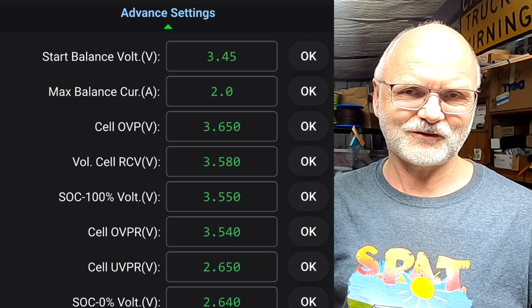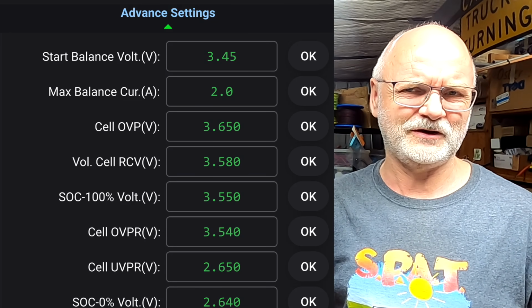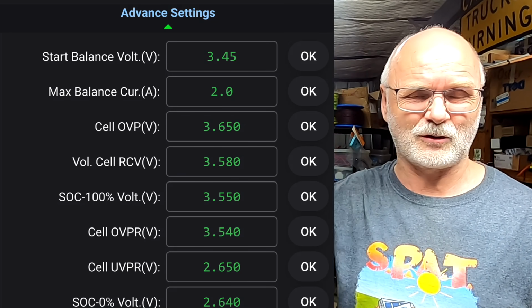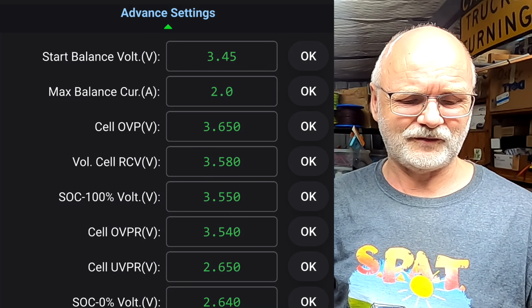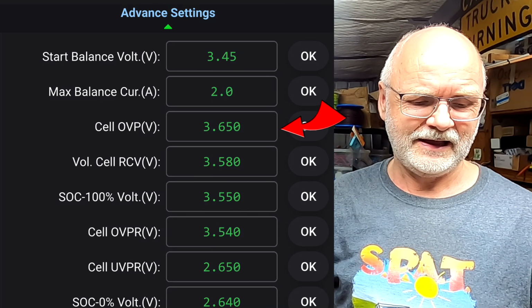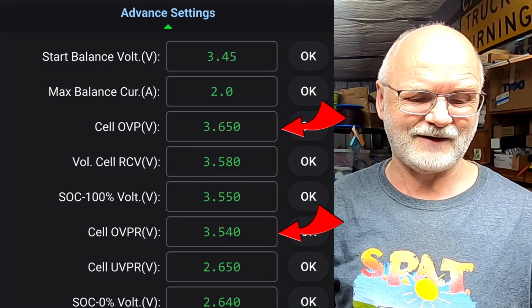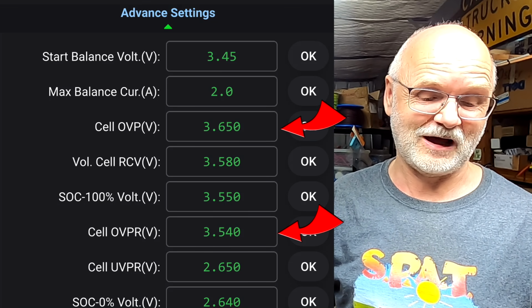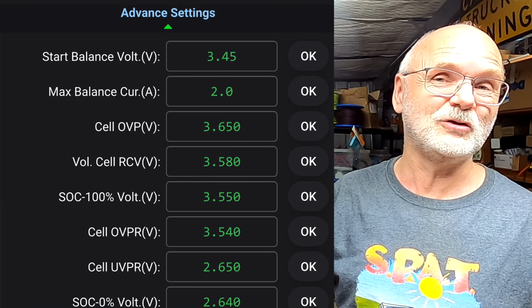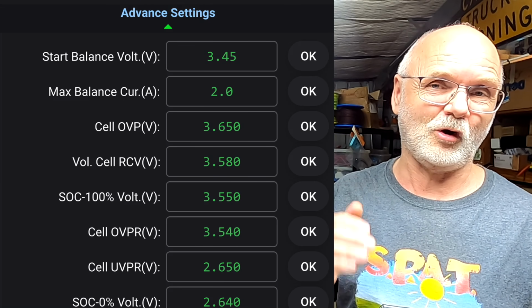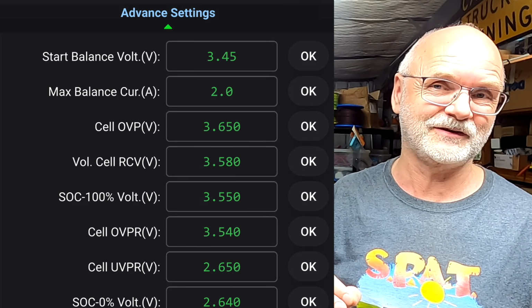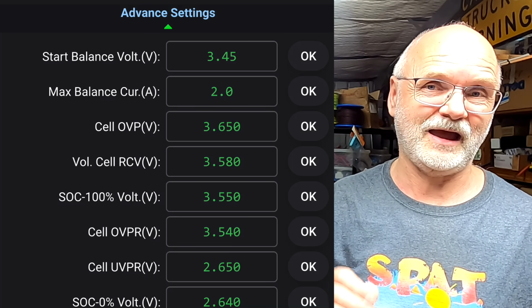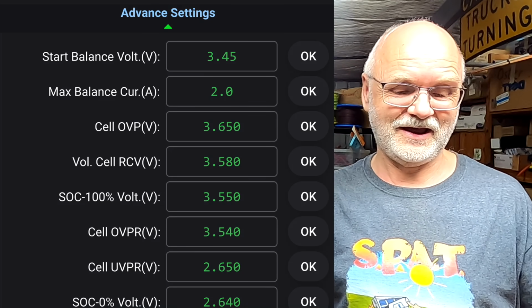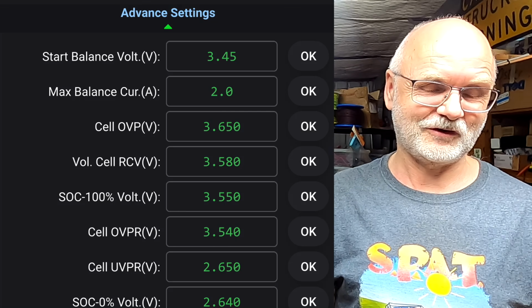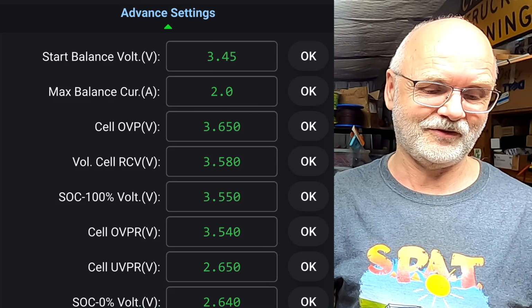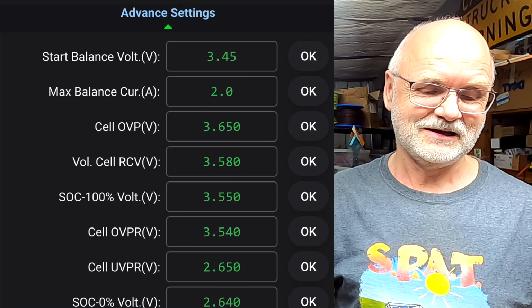By the way, I was complaining a bit about the order of these parameters because they seem a bit out of order. We've got the cell over voltage protection up here and then the cell over voltage protection recovery three parameters further down. They explained that this is user friendly because you go through all the values starting with the highest at the top and go lower with every value you're setting. Well, I cannot really confirm that because my balance voltage is a lot lower than my cell over voltage protection, so I'm not sure.